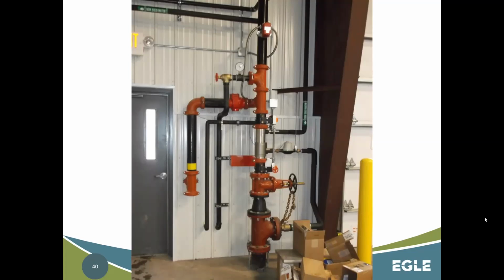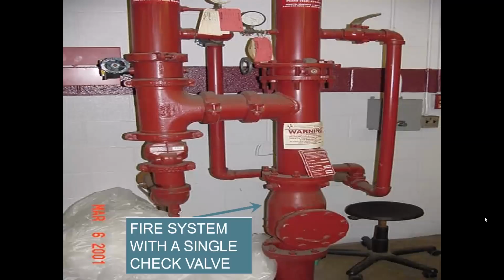This is another fire suppression system, and the issue with this one is that this fire suppression system only has a single check valve on it, which is not a recognized backflow preventer.